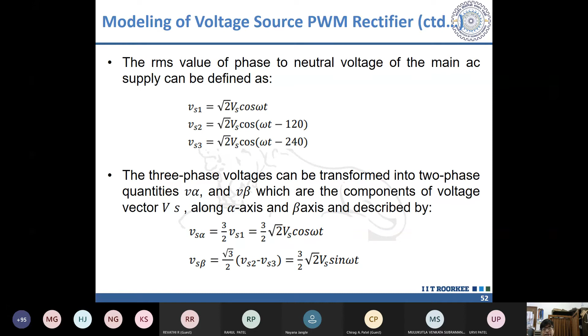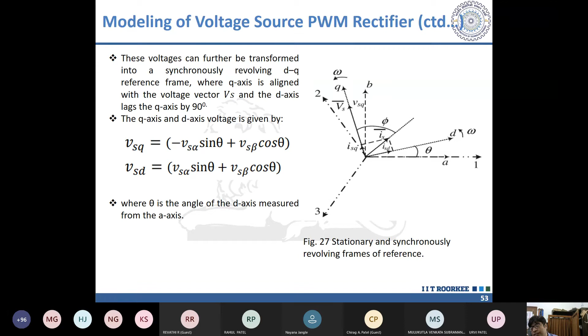Once we transfer it to the alpha beta frame, we rotate that alpha beta frame with the synchronous frame of reference. Here it is quite easy, unlike the motor, where it has to be fixed on the stator frame of reference or rotor frame of reference. Here you've got a PLL from the voltage, you fix it, and then this will be your P, Q and the VD, and thus you can have a vector control where we align phase A with the D axis, and thus we say unity power factor operation has been achieved.